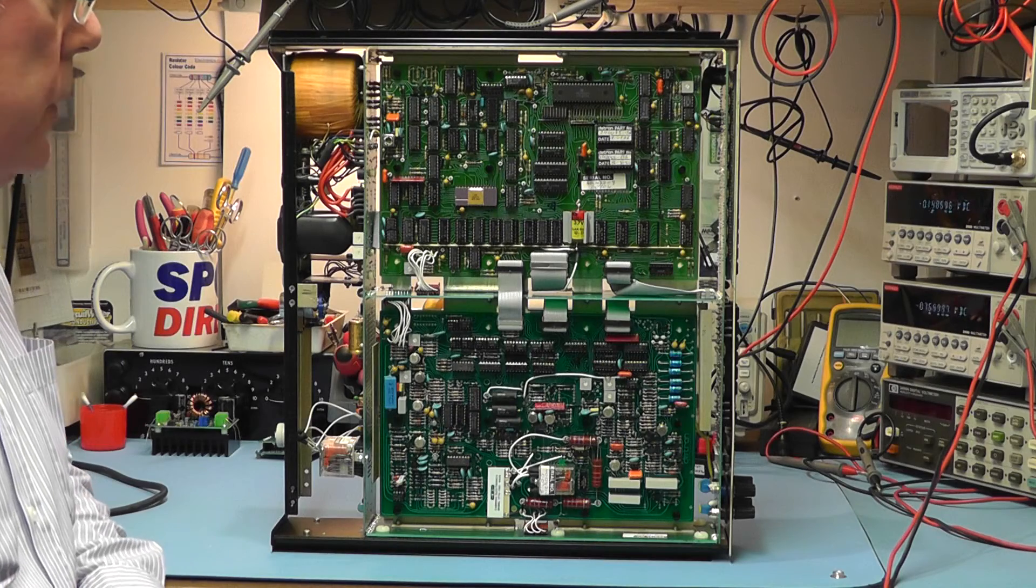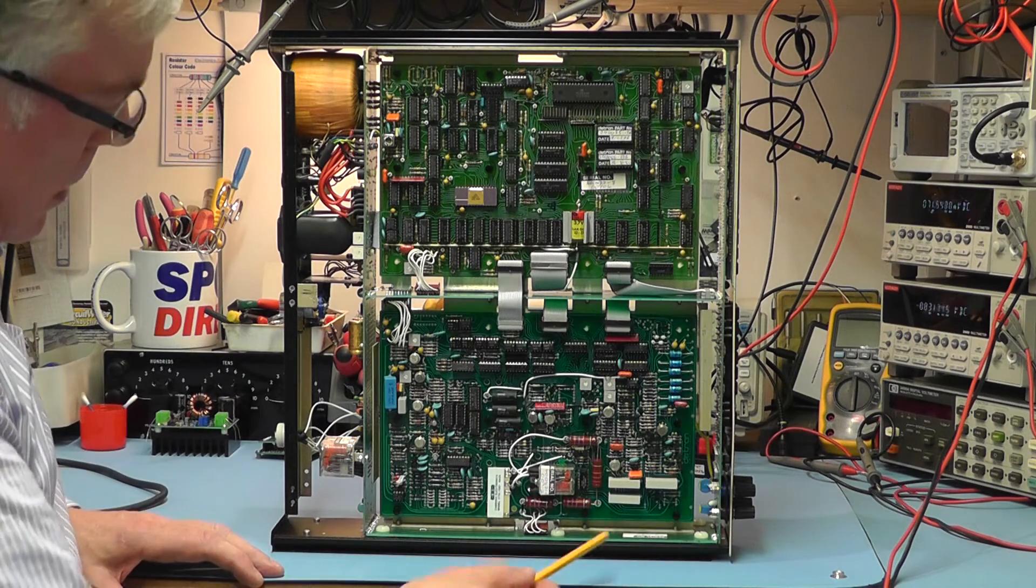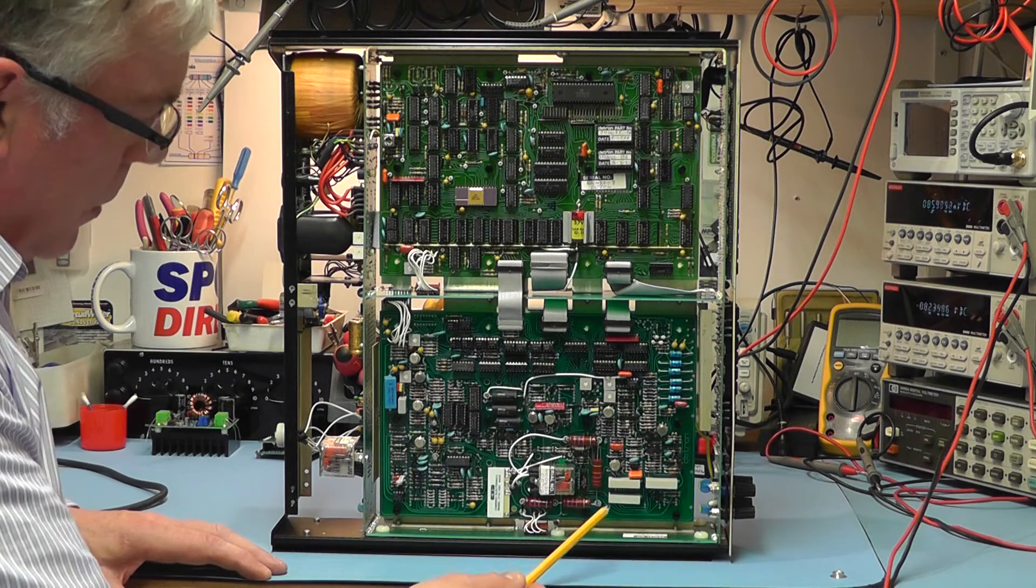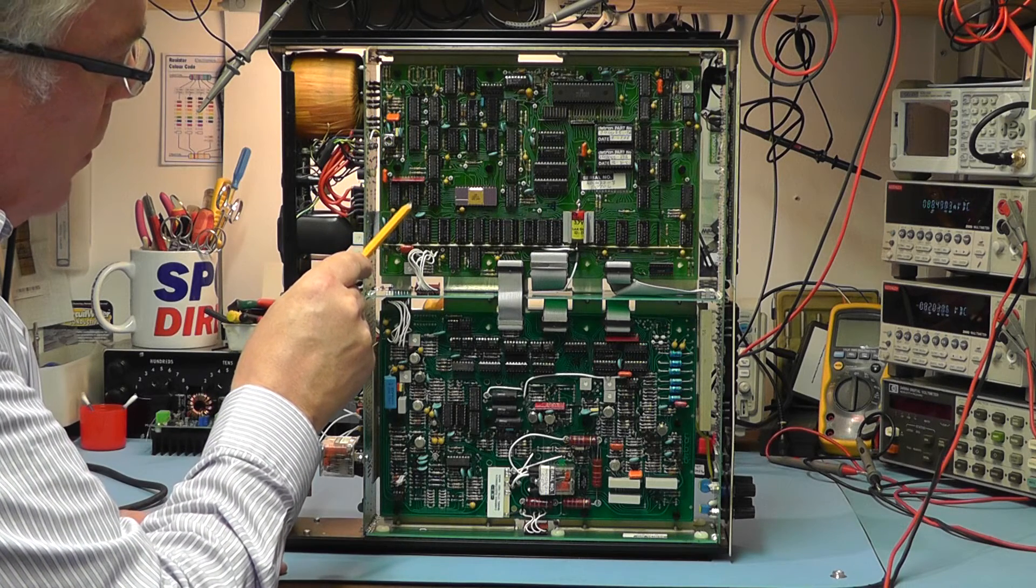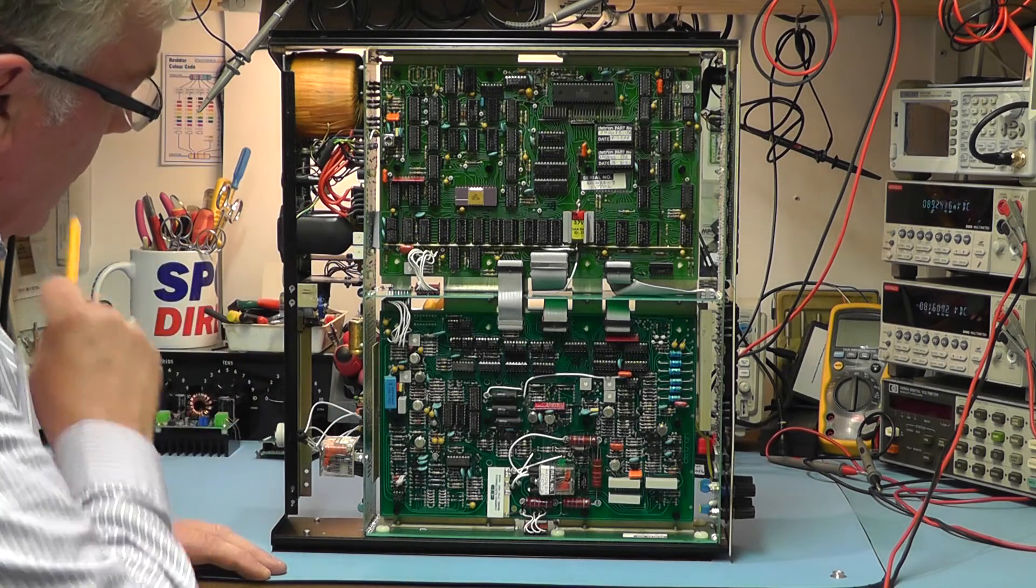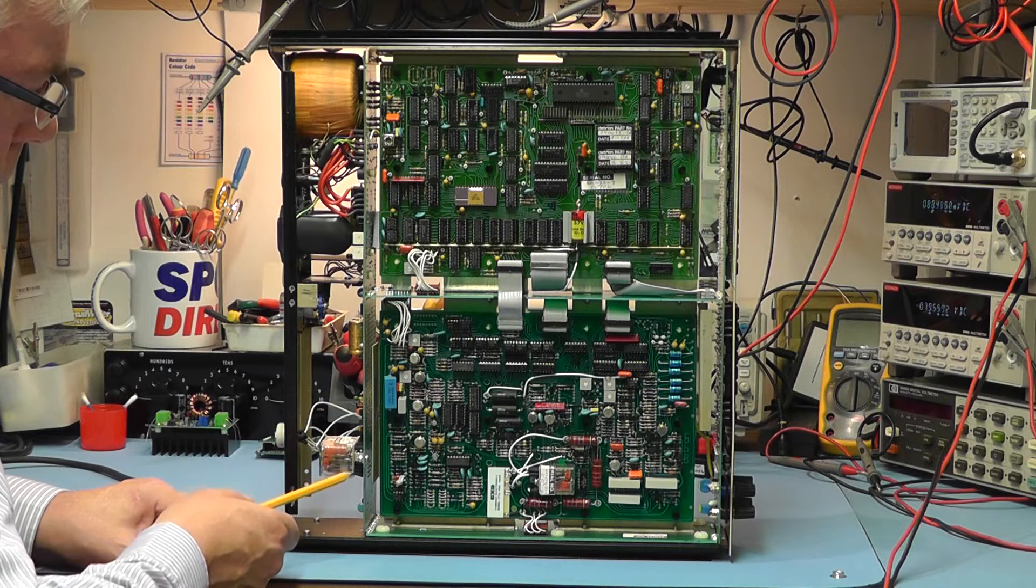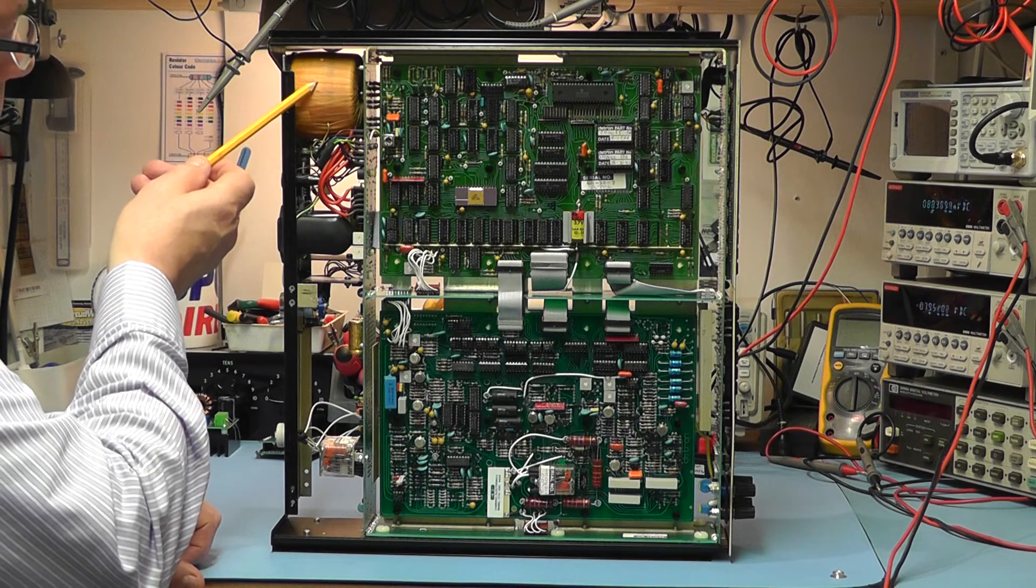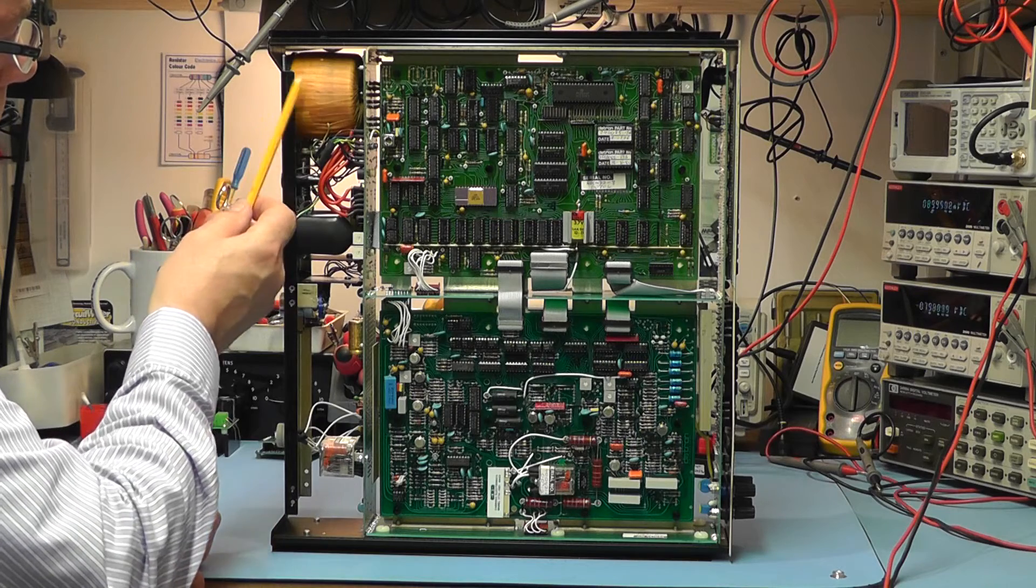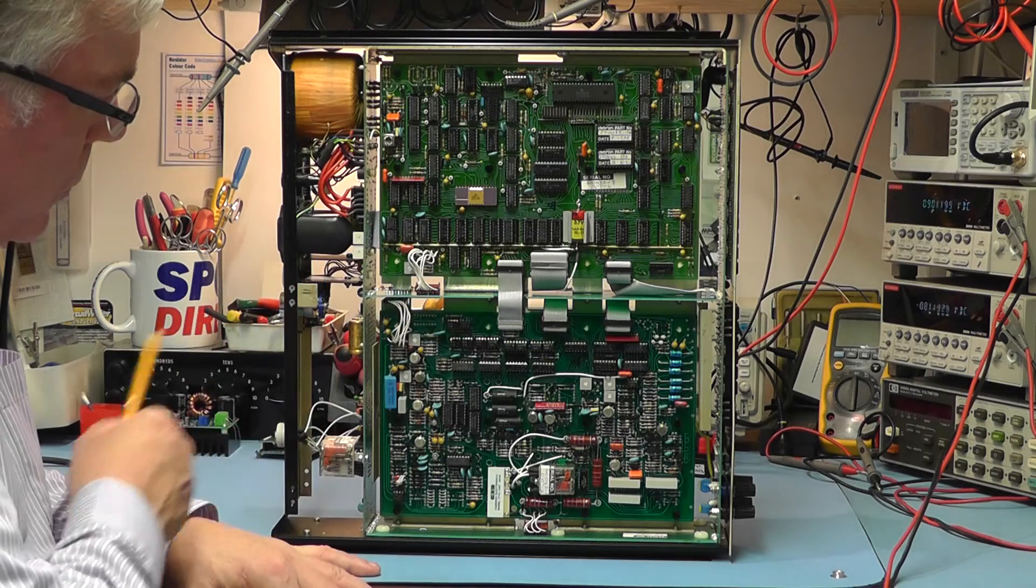Okay here we can see the inside, the top part of the meter itself. The front panel is there on the right. The bottom module here is the main analog circuitry for the meter or the input circuitry and the reference voltage, etc. And the other printed circuit board here is the digital board with the microcomputer on there to control the function of the meter. Down here at the back we have the switching relays and the switching circuitry switching to the back connectors for the meter, and here at the top, at the back we have the main power supply. There you can see the toroidal mains transformer. It is in fact two toroidal mains transformers and they've been strapped together. So let's zoom into each part of the meter and have a look in more detail at these modules.